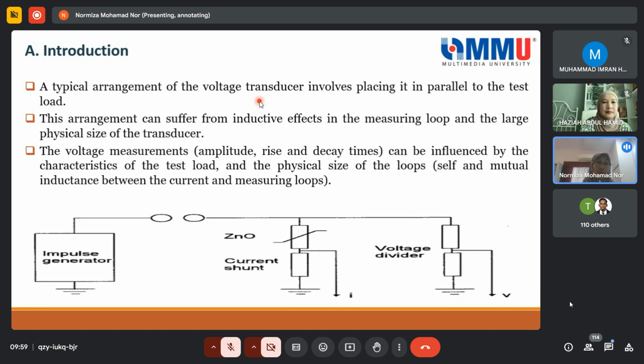A typical arrangement, or in fact, when you do the testing in other subjects as well, maybe you have come across this already, which is the source. Okay, you can say that this is the source, and then this is the zinc oxide or the test load, and then this is the current measurement, normally a shunt, or current shunt, here. And then parallel to that is the voltage measuring device, which in this case is the voltage divider. So this is the typical arrangement. I think if you do other subjects as well, such as circuit theory from your first year, or power systems analysis, normally this is the arrangement where the voltage measuring device is in parallel with the test load.